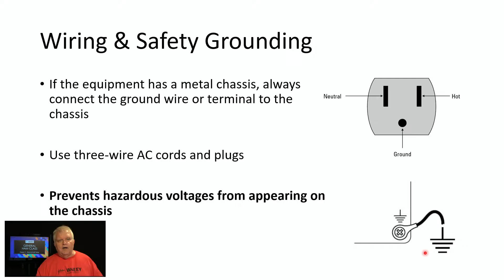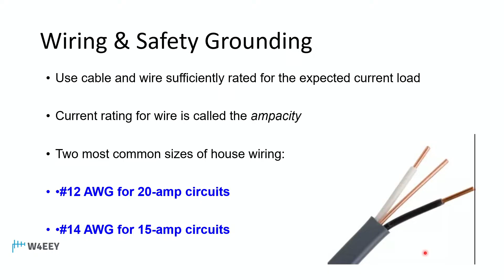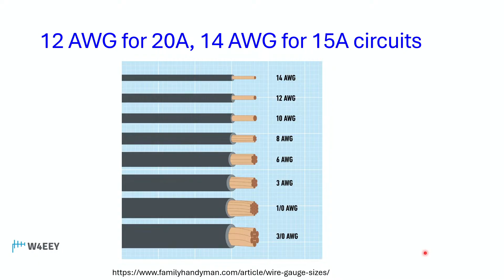Use wire and cable that is sufficiently rated for the expected voltage and current. The current rating of wire is called its ampacity—the capacity for carrying amps. The two most common sizes of house wiring are number 12 American wire gauge, used for 20 amp circuits, and number 14 American wire gauge, which is thinner and appropriate for lower ampacity 15 amp circuits. Here's a slide showing various American wire gauge sizes, all the way up to 3/0 at the bottom.